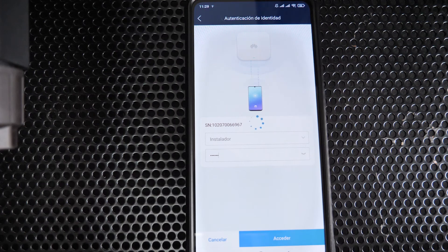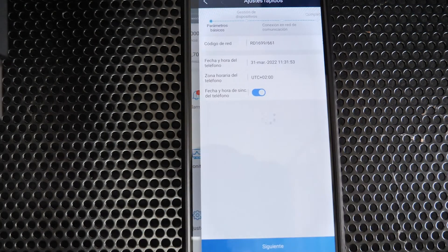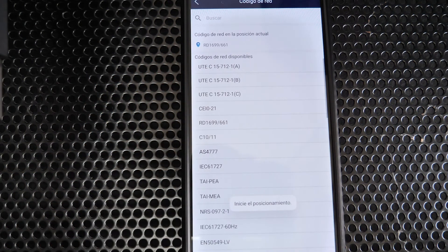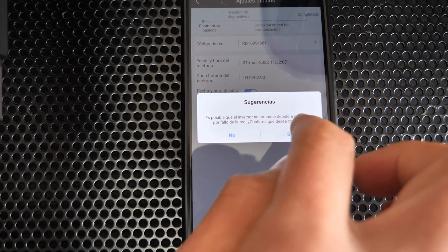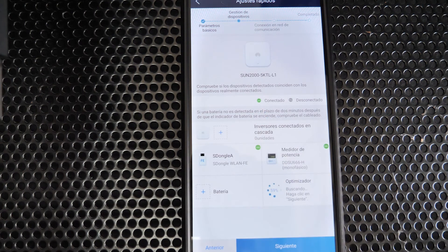From FusionSolar, go to Quick Settings to perform the commissioning. Here we have to select the grid code of the corresponding country — in this case Spain: RD 1699. The date and time can be left to synchronize automatically. In the next step, check that the energy meter and the WLAN FE dongle have been detected correctly.